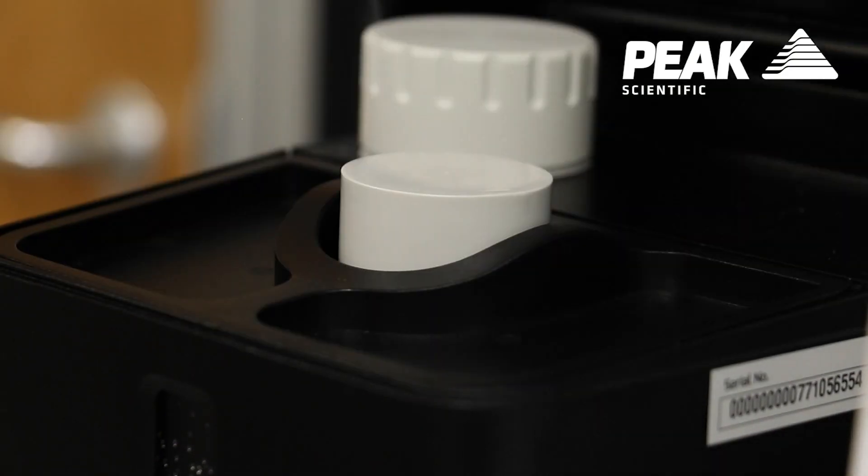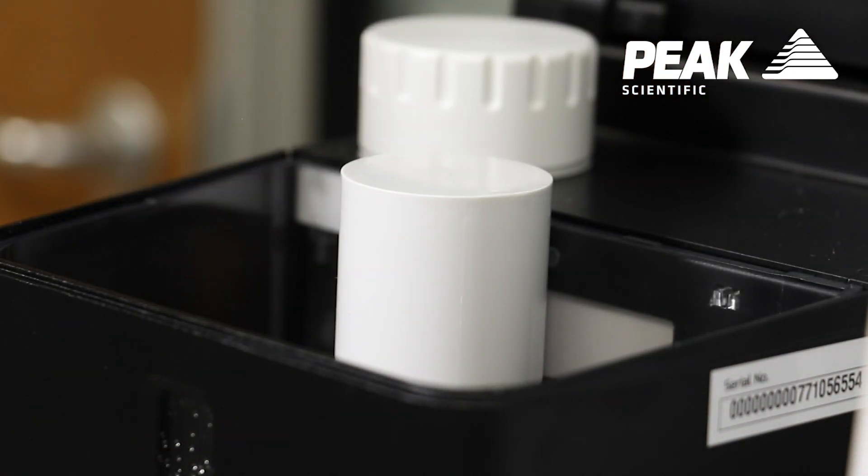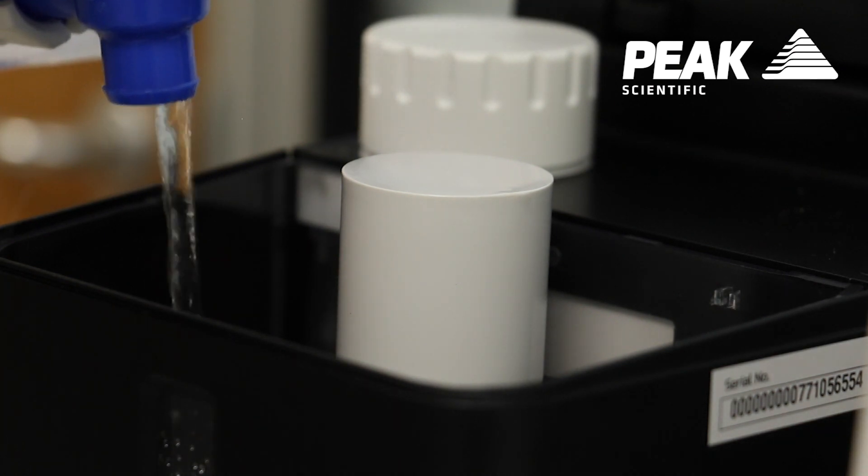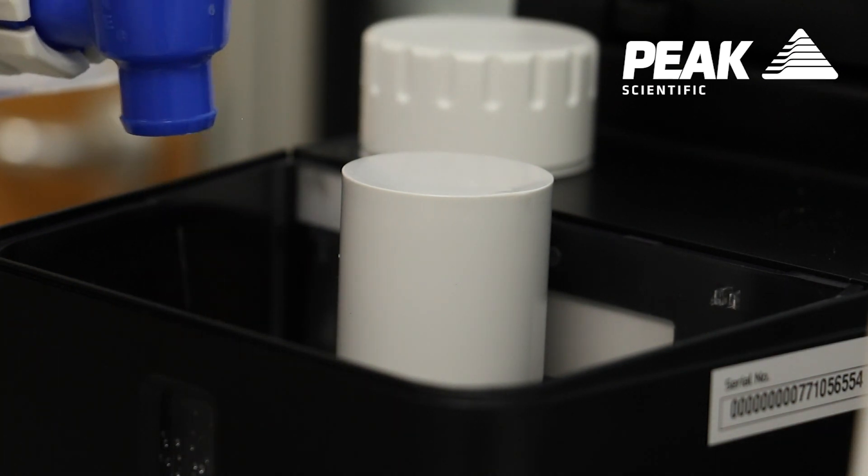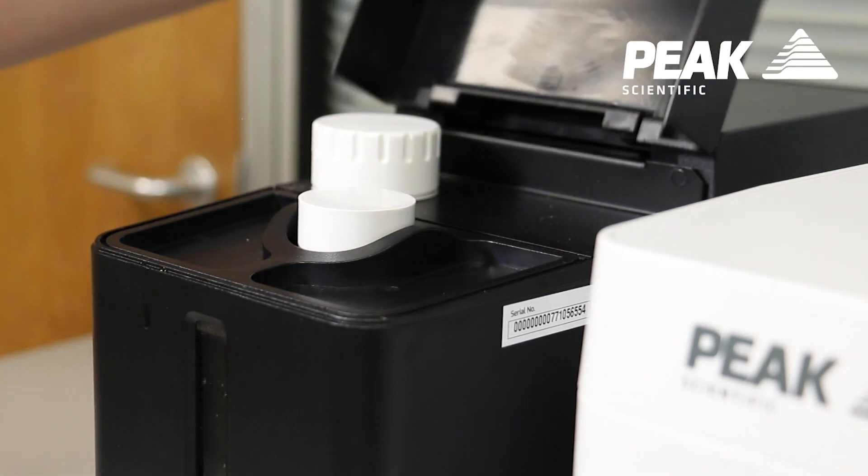The standard model will be equipped with a manual fill. We will also offer an option for auto water fill with a pump that will pump water in, and we will also be offering a system with pressurized water fill. This will enable customers to connect their generator straight to a deionized water supply.